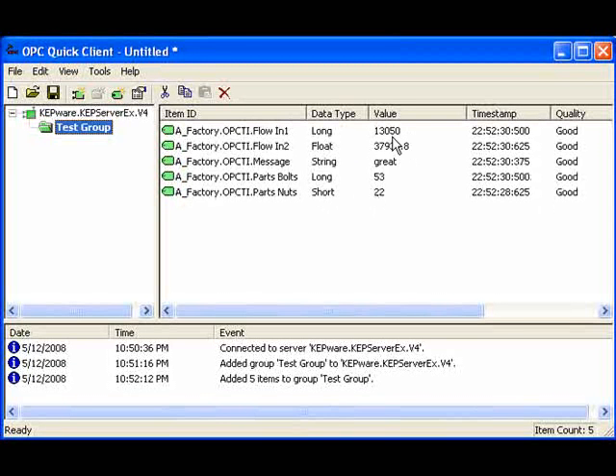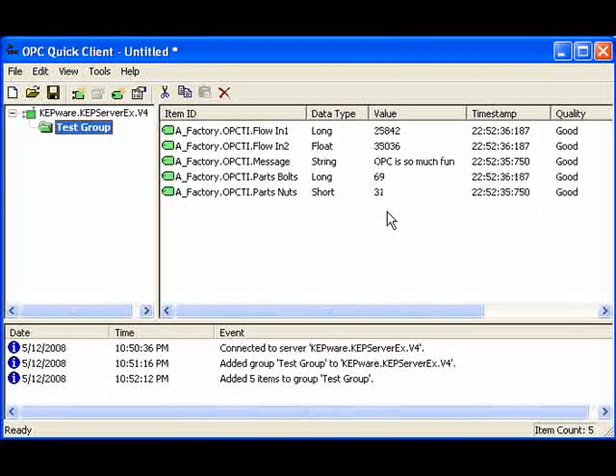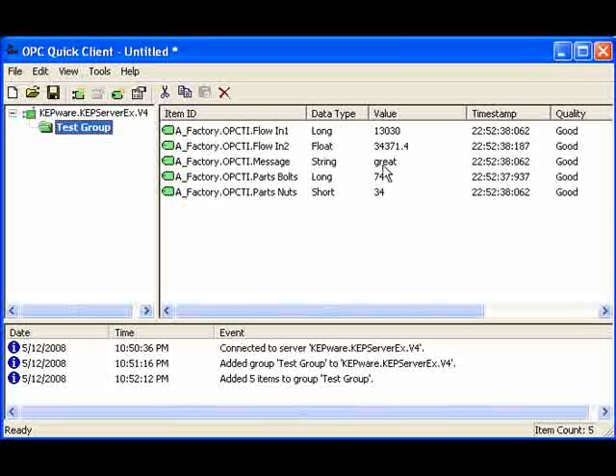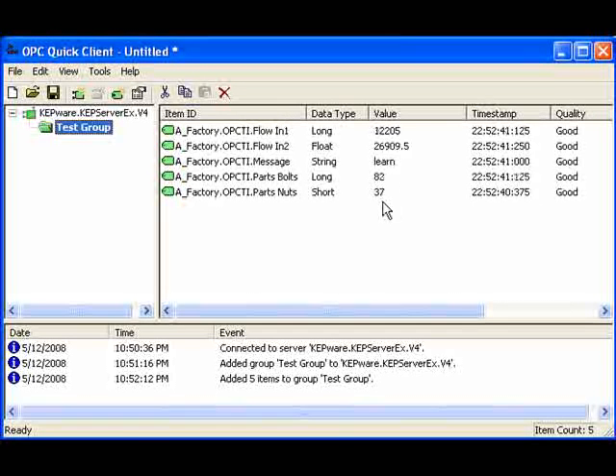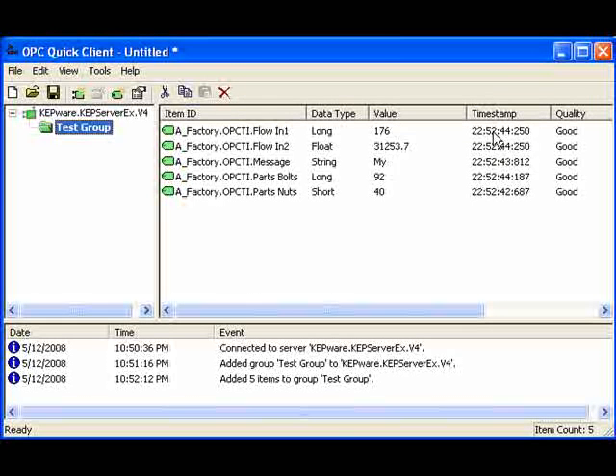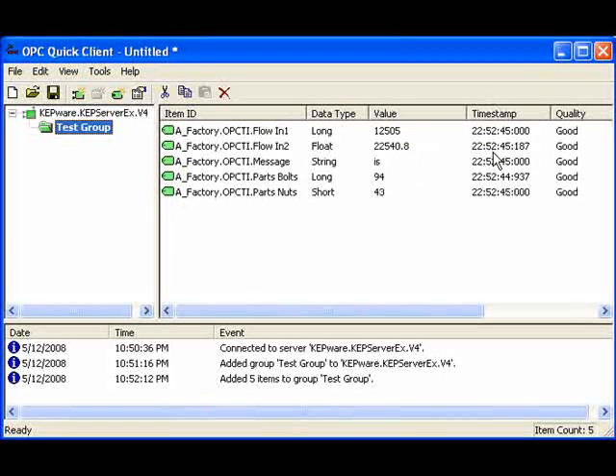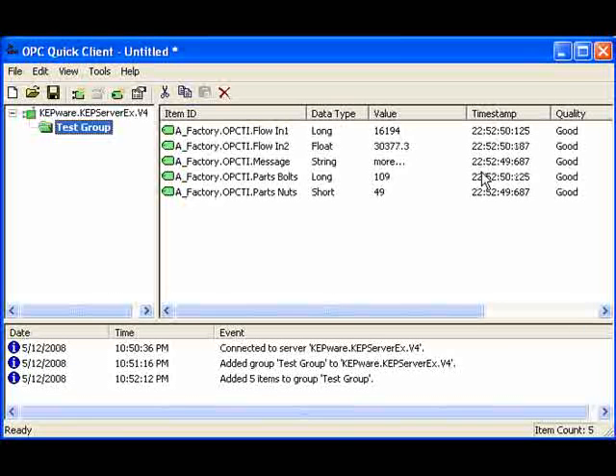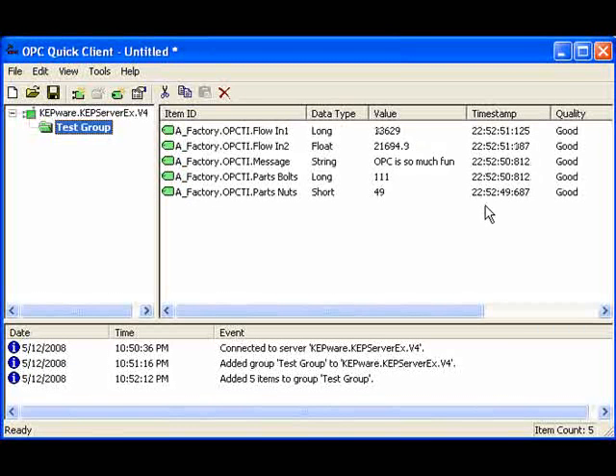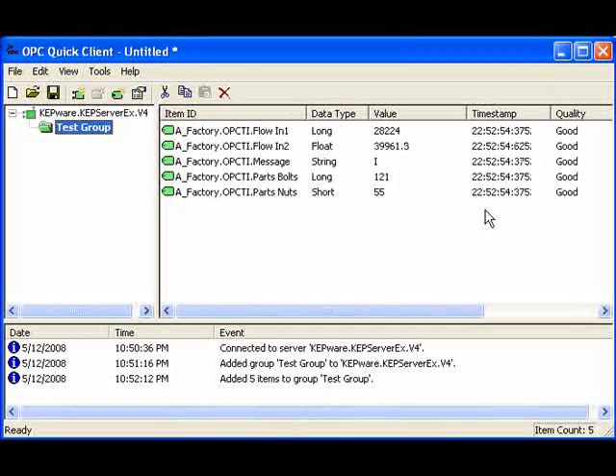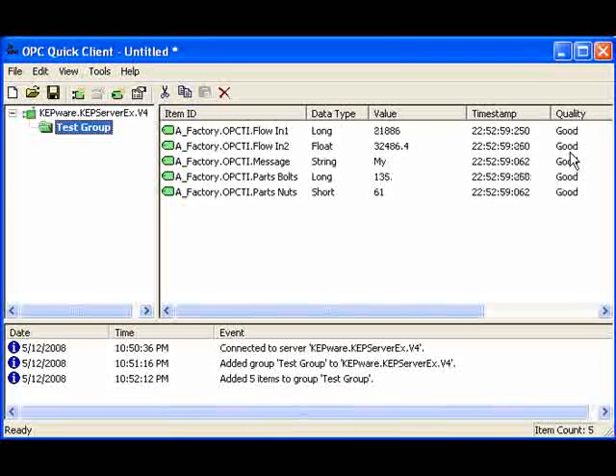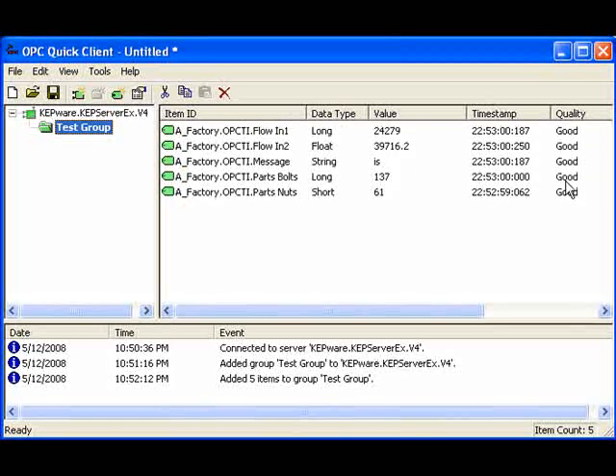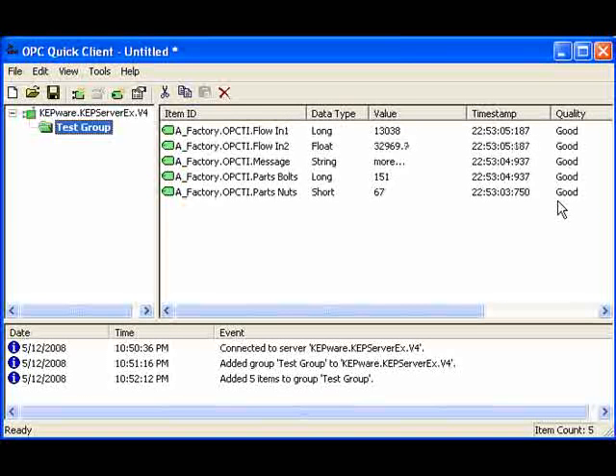We can see that our values are changing automatically. So in fact, here we are looking right inside our server, and these are the values that are available inside our server. Some values are changing quickly, some are changing slower. And we can see the timestamps. Here are the timestamps and they're changing. Some again are faster and some are slower. It really all depends on the rate at which the values change in the OPC server or in fact in the PLC. In this case, we see that our quality is good, which means that all of the values that we're getting from our OPC server are of good quality.